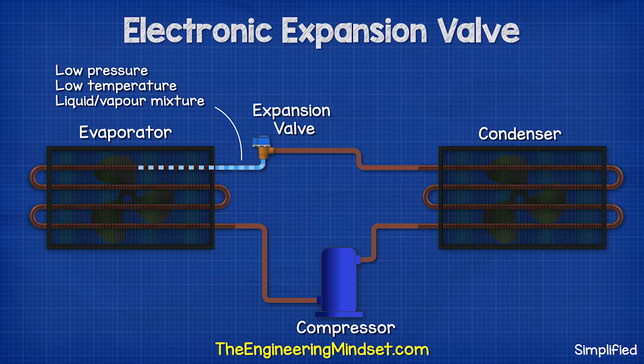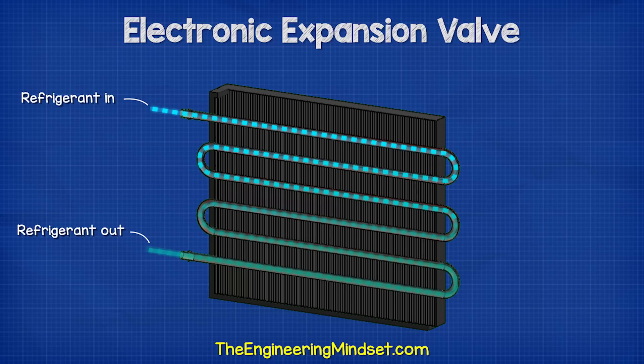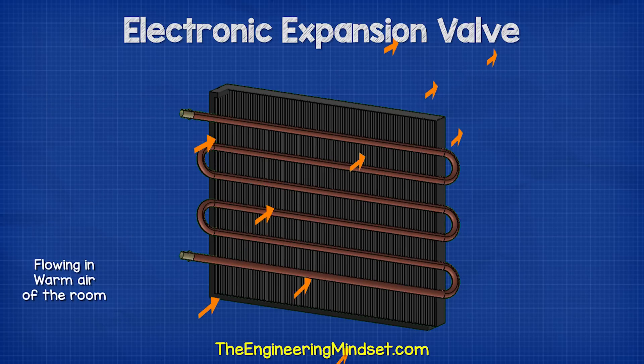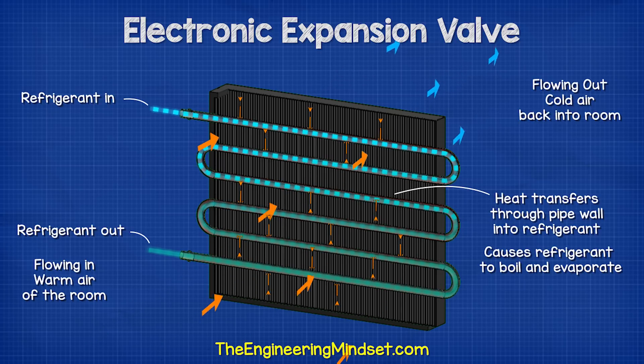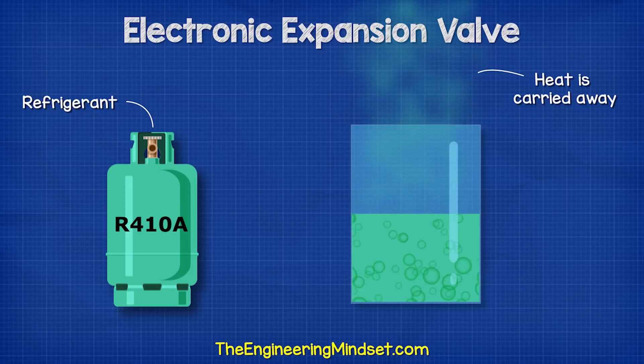The refrigerant is entering the evaporator as a low pressure, low temperature liquid-vapor mixture. It flows on the inside of the pipe and at the same time a fan is moving the ambient air of the room over the outside of the pipe. This causes the refrigerant to boil. It will absorb the heat from the air through the pipe wall and then it evaporates.